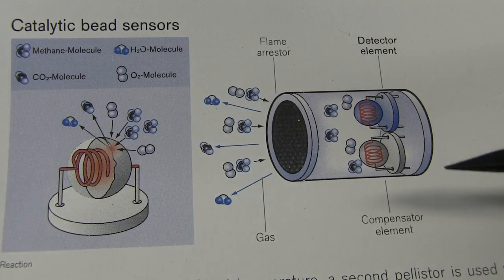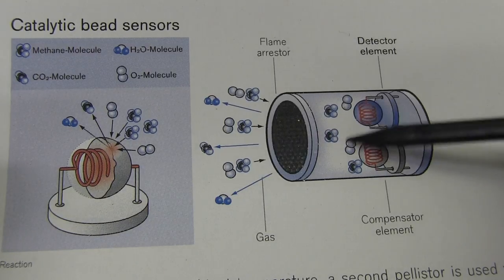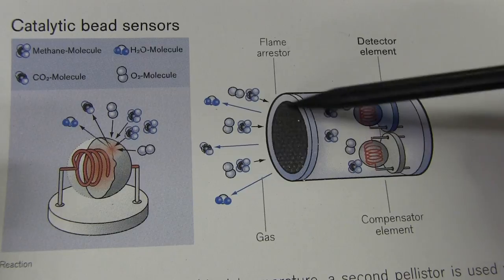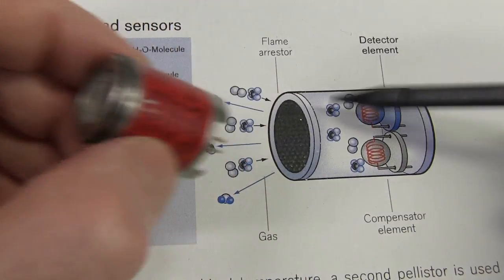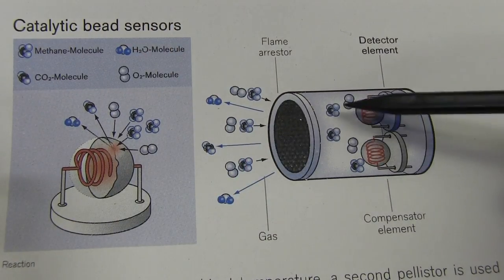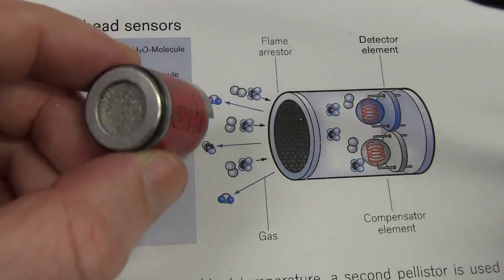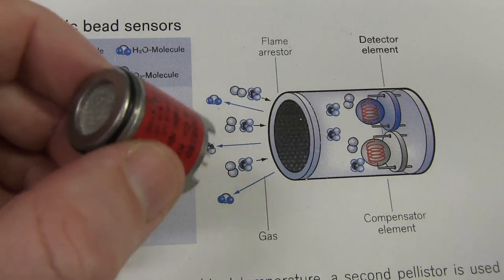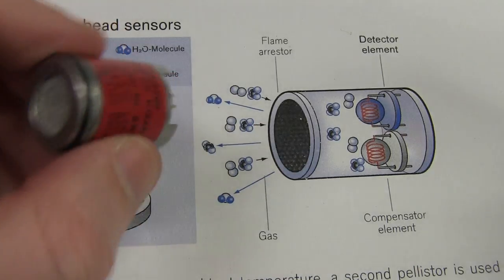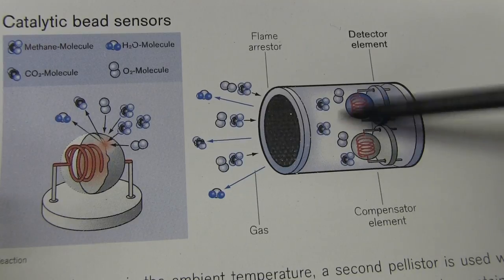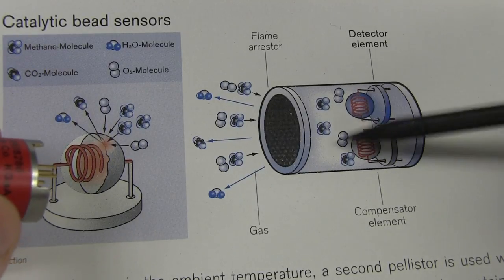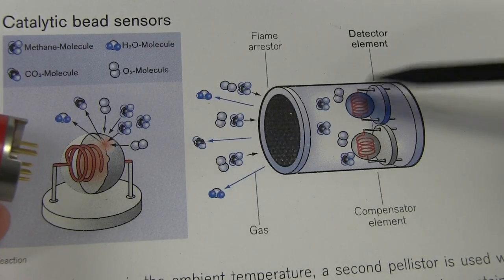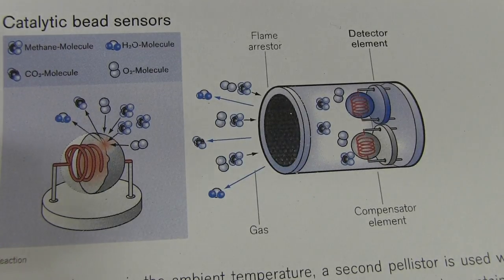I'm not sure exactly what temperature it gets to, but it heats up very hot, and what it does is actually burn the gas inside. That's why you need the flame arrestor here, because you don't want it to catch alight inside and have flames shoot out with these combustible gases. So that's funny, in an intrinsically safe device, they're actually burning the combustible gas you're trying to detect. Hilarious. The more combustible the gas in there, the hotter it gets, which changes the resistance of the detector element, a platinum coil. That's pretty much all there is to it. It's rather neat, I like it.